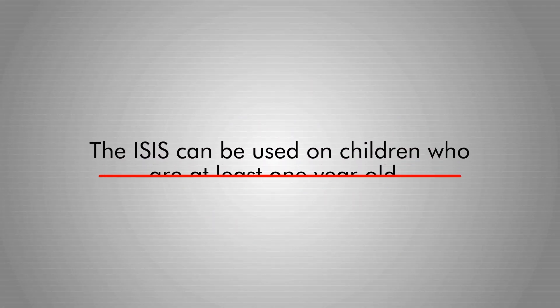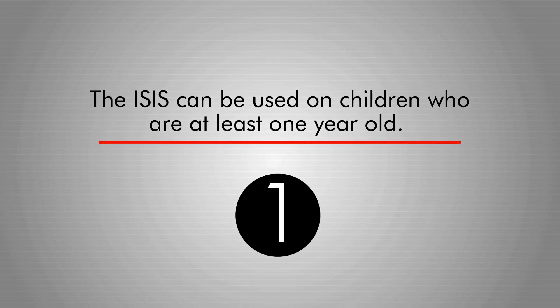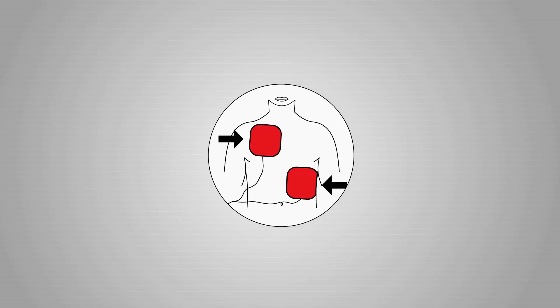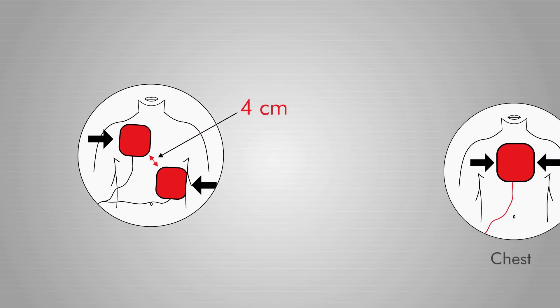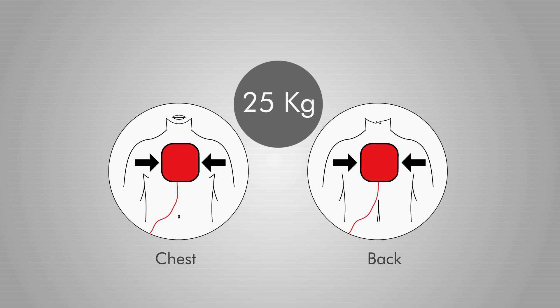The ISIS can be used on children who are at least one year old. The following precautions are to be taken when using this device on patients between one and eight years of age: use child-sized pads found in the InstraMed dispenser. Should it not be possible to position the pads at least four centimeters apart, place one on the child's chest and the other on their back. This applies to patients weighing less than 25 kilograms as well.